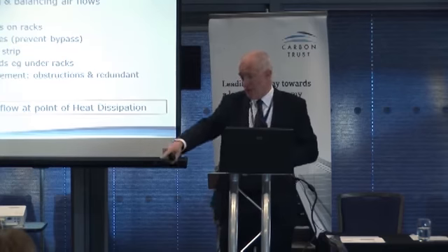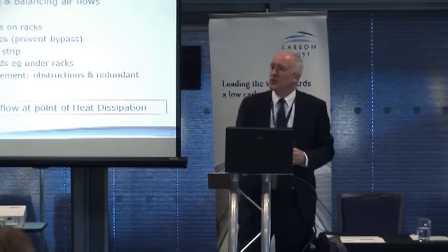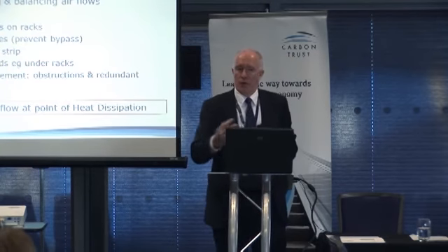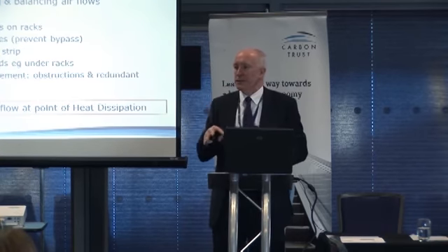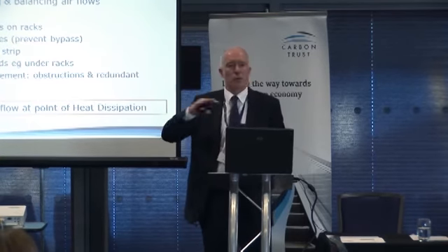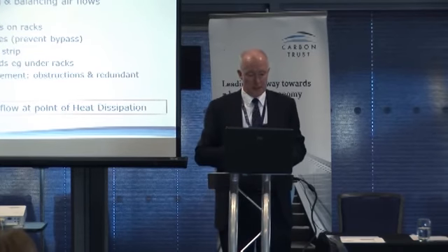And they said, right, well, we better move that diffuser from the cold side into the hot side, because it's so hot over here. And of course, they didn't appreciate what they were doing. So very often when we go into computer rooms, the whole thing is being mixed up. And we need to relocate things and redesign it, because everyone's forgotten what it's about in the first place, if they knew in the first place at any time.